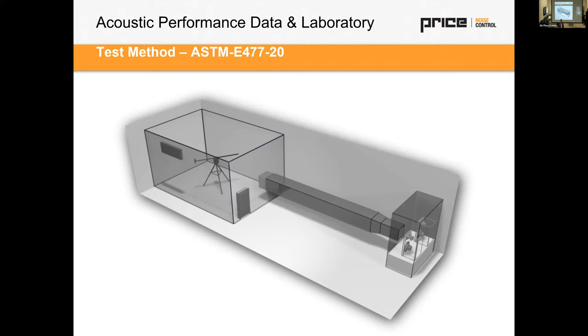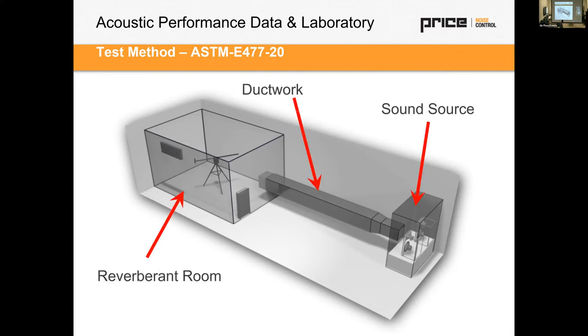Silencers primarily remove noise from a duct system. When you have a fan or an air handler or some sort of ducted path, the silencer will absorb and attenuate that noise. The setup that we typically use looks like this, where we have a source chamber, the ductwork, and then finally a reverberation room. And we use this test setup for measuring the amount of acoustical absorption and insertion loss that silencers provide.